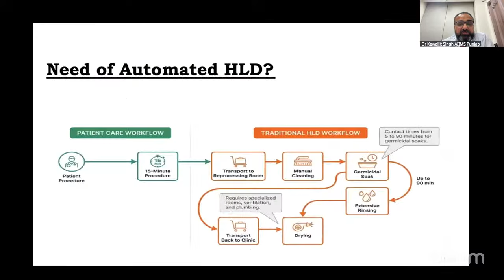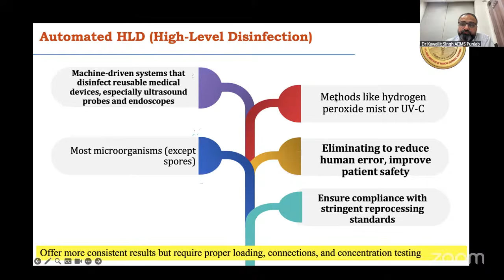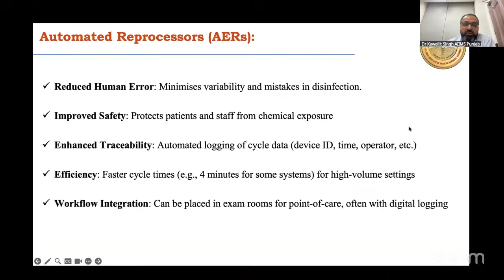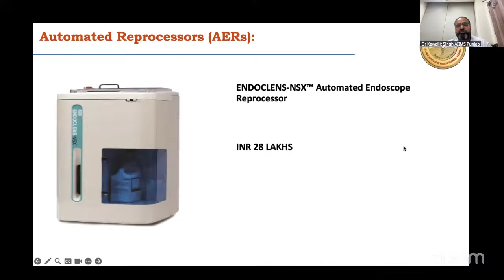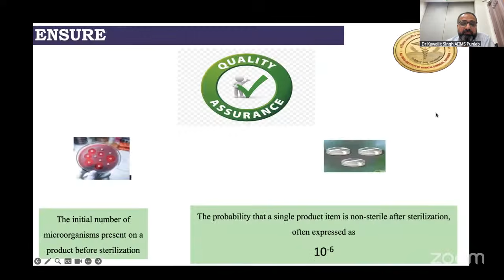Now, automated HLD has taken the place of manual because of the time-consuming, complex manual process and exposure of the manpower to the chemicals. The advantage of automated machines is that they disinfect the medical devices very quickly, eliminating human error and improving patient safety. These are some examples of the automated endoscope reprocessors that are available. The cost is very high, 28 lakh, 55 lakhs and so on.